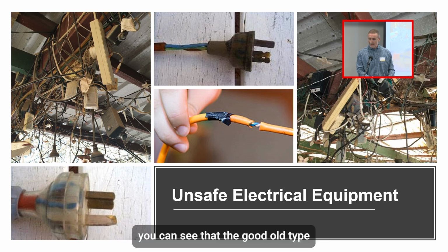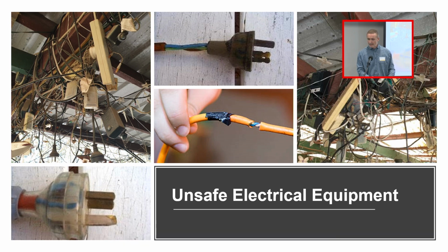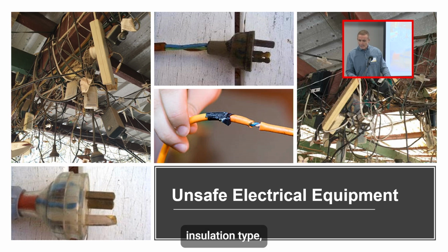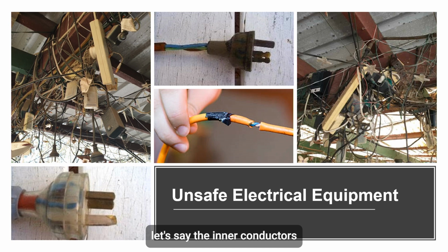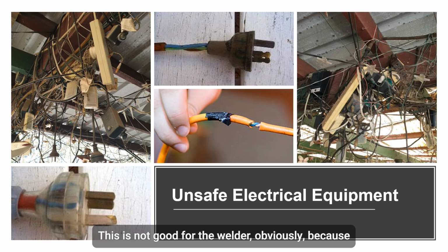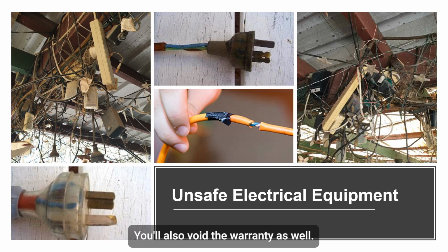Some of the images on the slide show the good old insulation tape. I see the inner conductors on one of those extension cords are exposed, so you've only really got a couple of mil of rubber protecting you. It looks like the earth pin on one of those plugs has been filed down, which I've seen a few times, welders doing that. This is not good for the welder, obviously, because it's designed to have a bigger earth pin to allow for fault currents. You'll also void the warranty as well.